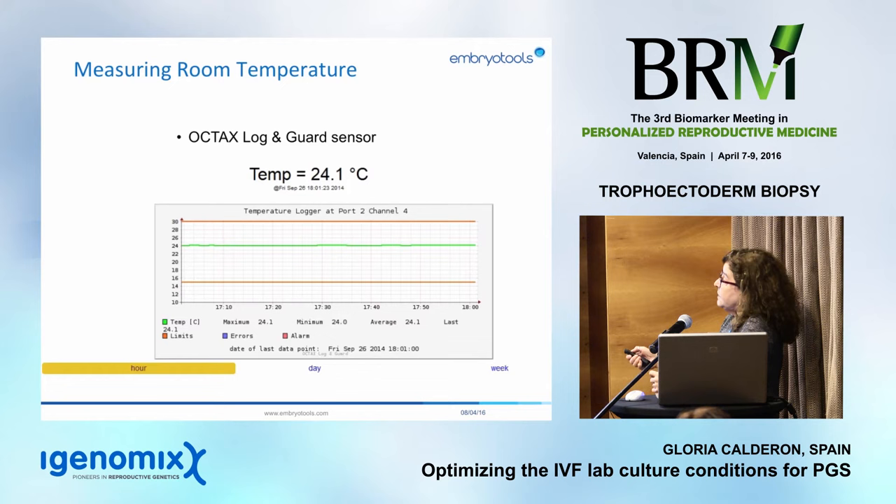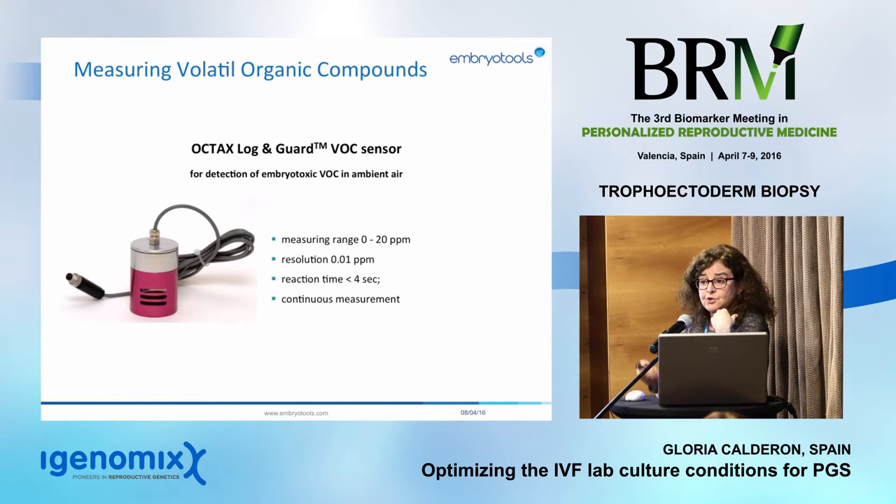Room temperature should never be higher than 24 degrees — we need to feel a little chilly to avoid contamination by fungus and bacteria, and to avoid forcing equipment to work harder. We are now very happy with the OctaX Log & Guard VOC sensor. Its measuring range is 0 to 20 ppm, with high resolution, a reaction time of less than 4 seconds, and continuous measurement — because the amount of VOC changes rapidly. As far as we know, it is the only continuous online VOC sensor available in the market.